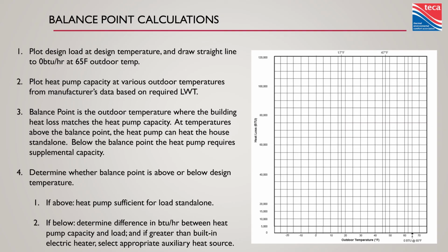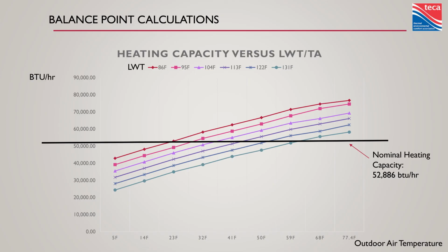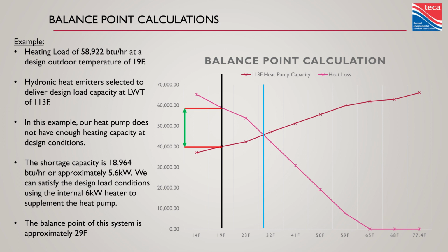Along the bottom of this I have outdoor temperature. On the left side is capacity. Here's a slide version of the output of a heat pump. The black line is the nominal load. Each one of these lines represents a different leaving water temperature and its capacity at different outdoor temperatures. So I can take a design heat loss right here, and I can say I need almost 60,000 BTUs at 19 degrees. So that's what the house needs, and as it gets warmer out, it needs less and less heat.